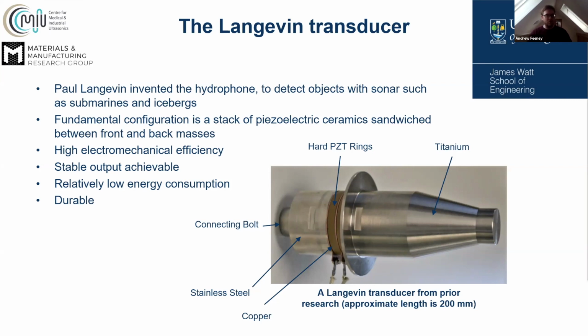The advantages of a Langevin-based transducer include high electromechanical efficiency, stable output, relatively low energy consumption, durable. But a lot of these properties come from the fact that we can use this type of piezoelectric ceramic. Lead zirconate titanate is PZT, and that's by far the most popular, based on its favorable, shall we say, properties at high amplitudes and high cyclic motion. For a transducer such as this, you also need to make various calculations when you're constructing it that you maybe wouldn't necessarily need to calculate for your modeling. So when I put this together, I calculated from first principles the optimum pre-stress for the ceramics, for example. And when I put it together, I found it worked really, really well.